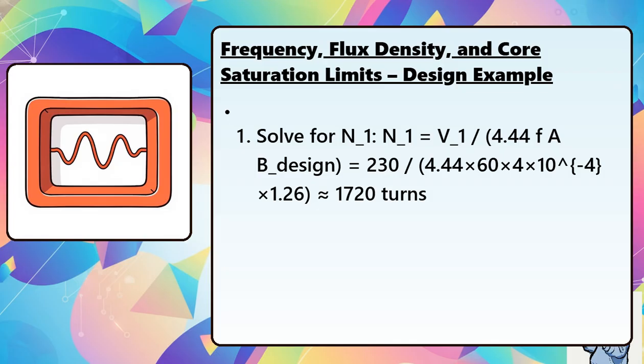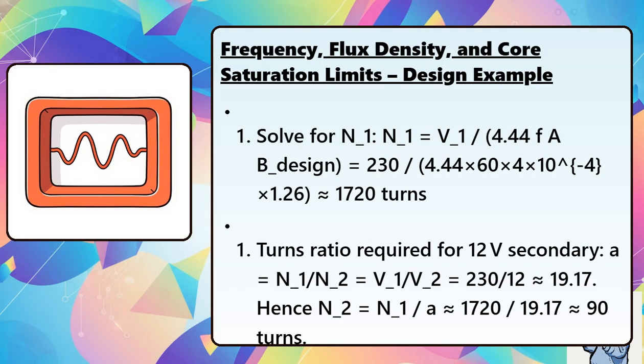2. Solve for N1. N1 equals V1 divided by (4.44 times F times A times B design) equals 230 divided by (4.44 times 60 times 4 times 10 to the minus 4 times 1.26), approximately 1,720 turns. 3. Turns ratio required for 12 volt secondary. A equals N1 divided by N2 equals V1 divided by V2 equals 230 divided by 12, approximately 19.17. Hence N2 equals N1 divided by A, approximately 1,720 divided by 19.17, approximately 90 turns.